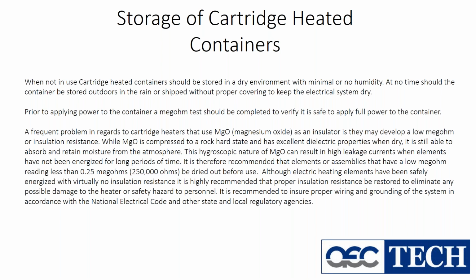So it's really good to have a slow, dry heat. Check the mega ohms, get those numbers from your supplier. When you do your own checks on site, if you've got less than 0.25 mega ohms, or 250,000 ohms, they need to be dried out before use.